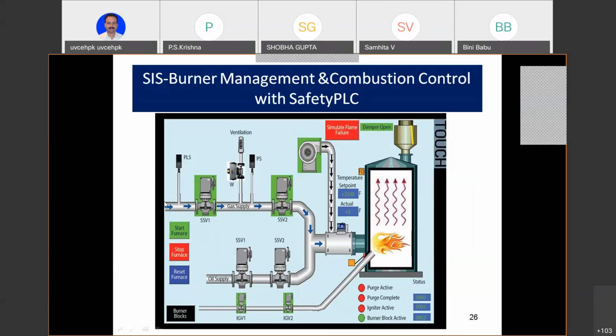Now, it's fired by gas, like our domestic gas, or by oil, and you select it by a selector switch and fire it. But how do you start this safety instrument system? It starts as follows: step 0, you go to this fired heater and you fire it. What are you worried about? What is the end goal? You wanted to make sure that the residential area near the plant you designed did not blow up, and you did everything to provide a safety instrument system.